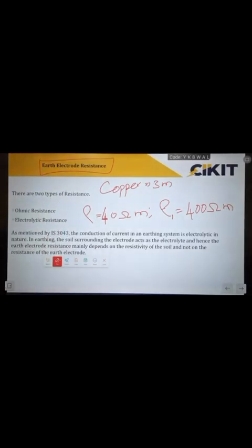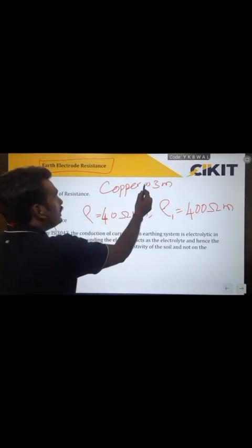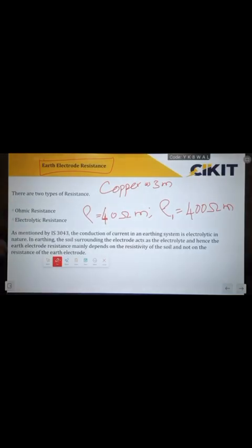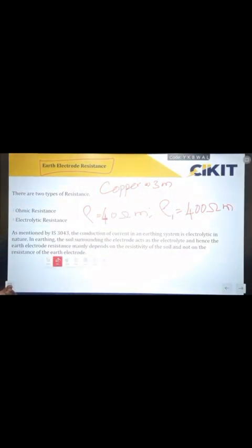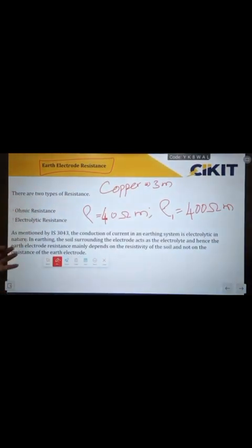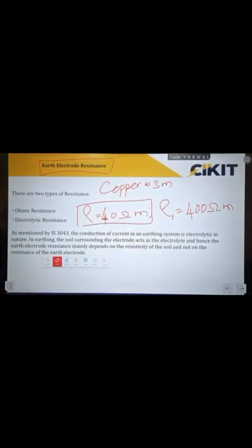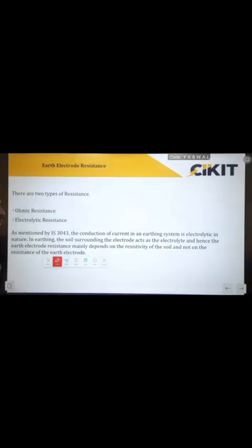The electrolytic resistance mainly depends upon the resistance of the surrounding medium and not on the resistance of the material. I cannot achieve in 400 ohm meter soil the same resistance value which I achieved in 40 ohm meter soil, because the soil resistivity is the deciding parameter in earth electrode resistance.